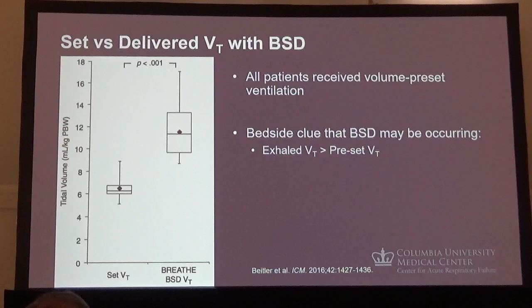But obviously that air has to come out somehow. And so if you look at the exhale tidal volume, you'll see much, much larger exhale tidal volumes than what the ventilator is suggesting on the inspiratory cycle side. And so I think there's an opportunity there, if you set your exhale tidal volume alarms relatively tightly, that this might be something you could pick up even if somebody has no experience with mechanical ventilation, just by having the alarm of what's going on.